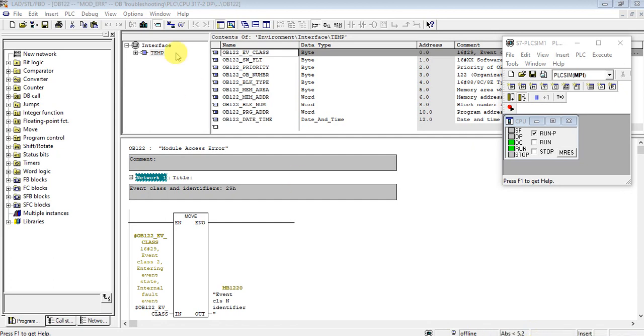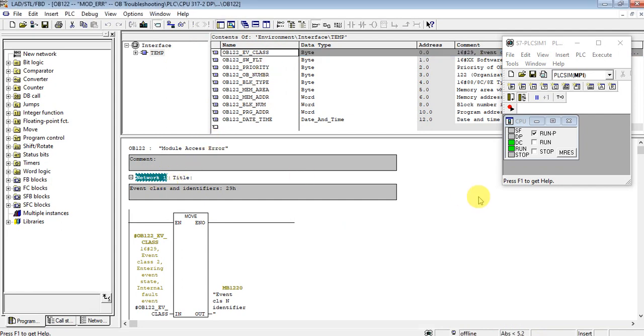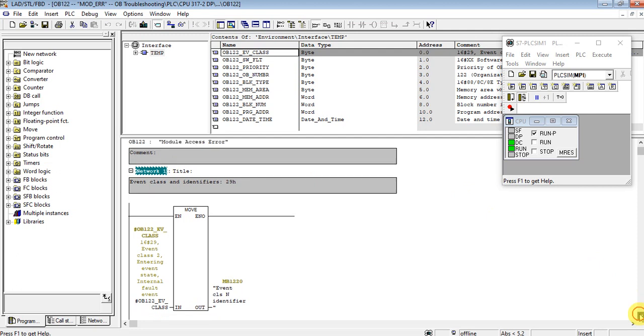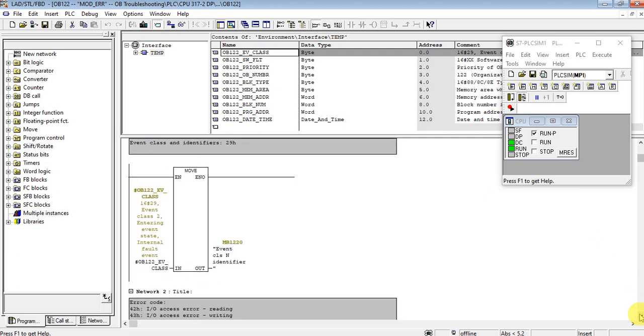Here is OB122 with its default variables. I'll use some of the variables that are most useful for identifying the problem location. For example, the event class variable — if there is an error, it will give us 0x29 in hexadecimal.